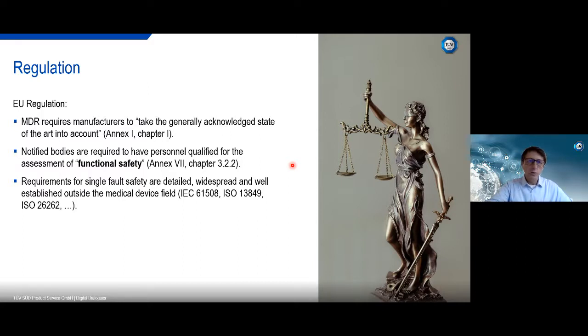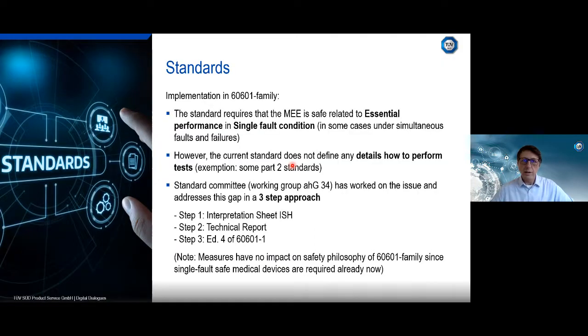When we want to go into more detail, we need to apply standards, and therefore we have to look at the 601-1 family. Here it says that medical electrical equipment has to be safe for essential performance in single fault conditions - this is said by the standard. However, at the moment it doesn't give any details on how to perform the tests. The 601-1 basic standard does not give any details how to perform the tests. That's a little bit a pity at the moment.